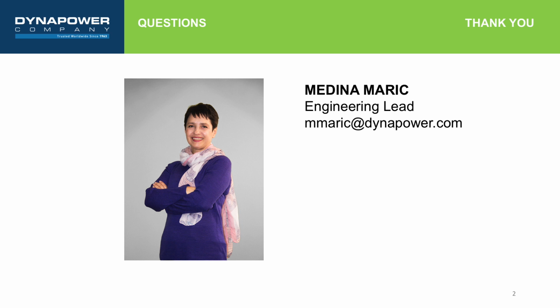And the question was related to specific selection criteria for the best application between diode rectifier, Thyristor rectifier, or chopper rectifier. There are two basic lines and two basic processes that will determine which power supply and which topology would be the best for the application. There is the process side of design and design parameters from the process specific to the customer, and the other would be electrical system factors. From the process side design parameters, we are looking at DC voltage and current for operating range that is required for the process, current ripple, current regulation accuracy, current regulation speed, DC voltage, DC power availability, and a redundancy concept for the customer, required overload capabilities.